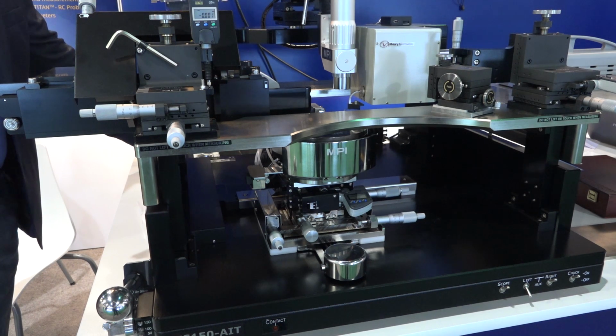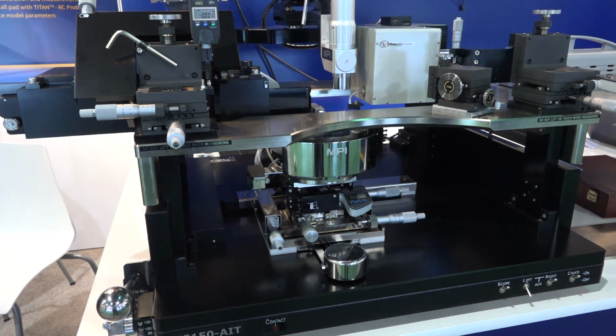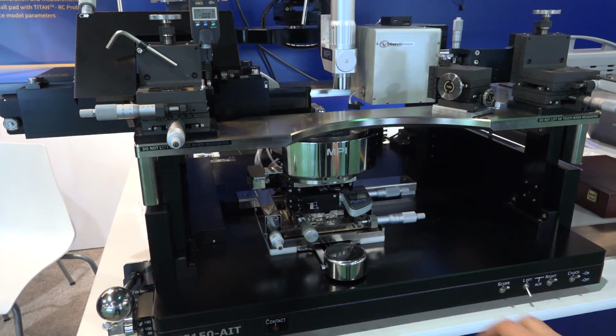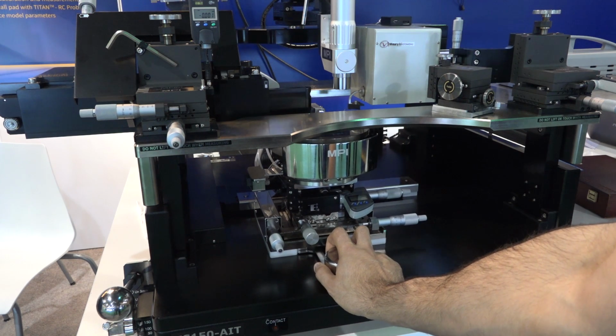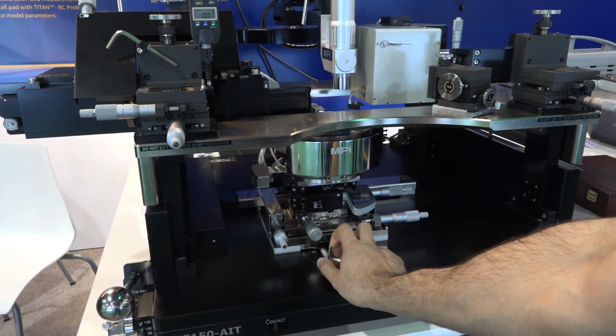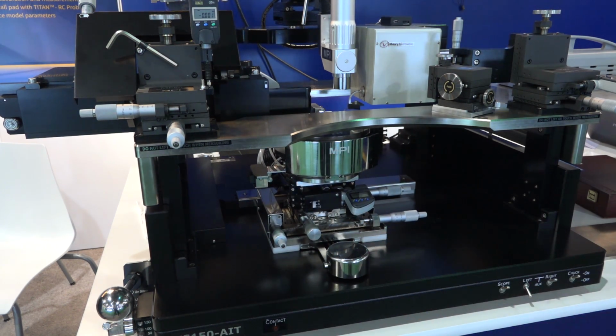And they have some really neat innovations. For instance, in order to move the chuck, if the instrument knows that you are not landed, it will allow you almost free movement of the chuck. So for example, right now the probes are not landed, so I can just grab this and move the chuck around with quite some ease, and large movements can be accomplished this way, where normally you would have to turn these rotation knobs forever to get to where you want.